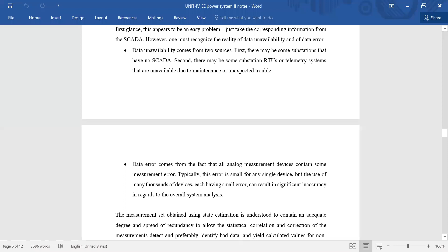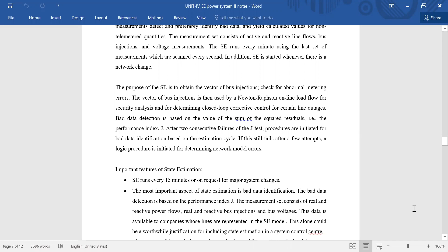Some features of state estimation: it runs every 15 minutes or on request for major system changes. The most important aspect of state estimation is bad data identification. Bad data detection is based on the performance index. The measurement set consists of real and reactive power flows, real and reactive power injections, and the bus voltages. This data is available to the companies whose lines are represented by the state estimation model. This alone could be a worthwhile justification for including state estimation in a system control center.